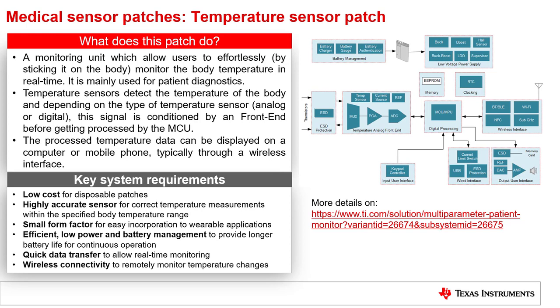The key system requirements for temperature sensor patches are: low cost for disposable patches; highly accurate sensor for correct temperature measurements within the specified body temperature range; small form factor for easy incorporation into wearable applications; efficient, low power, and battery management to provide longer battery life for quick data transfer and real-time monitoring; and wireless connectivity to remotely monitor temperature changes. A common block diagram for a temperature sensor patch is also shown in the slide.